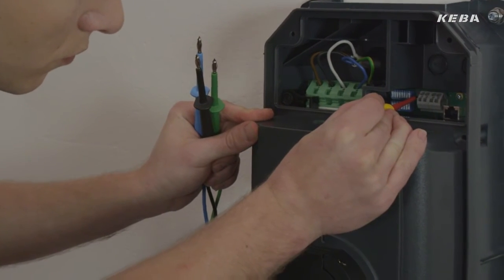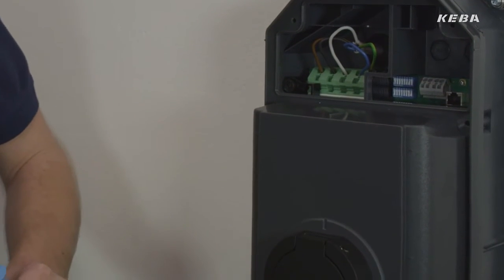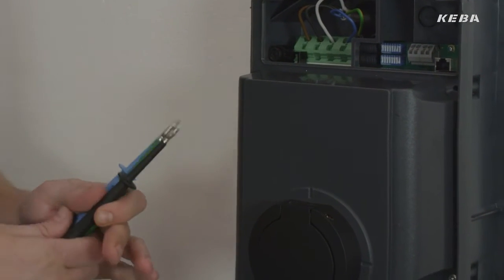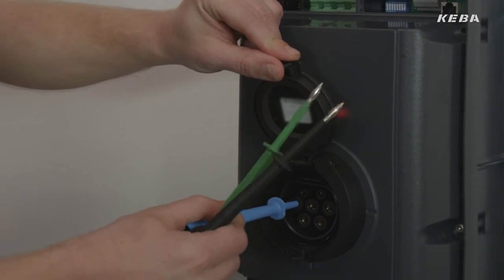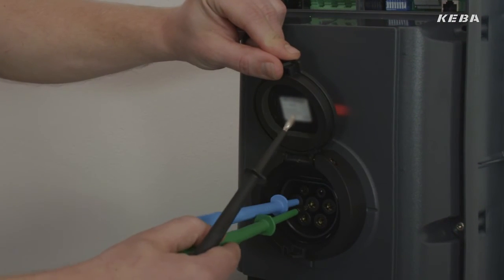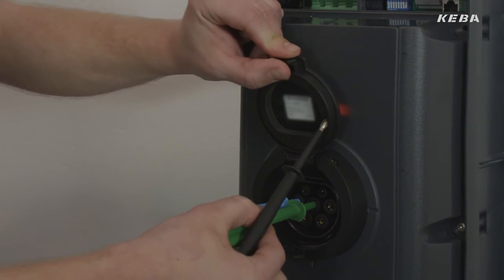By using the dip switches, the wallbox is also brought into commissioning mode. The KeContact P20 first performs a self-test and then allows testing of the installation. With this feature, an often expensive vehicle simulator is superfluous.